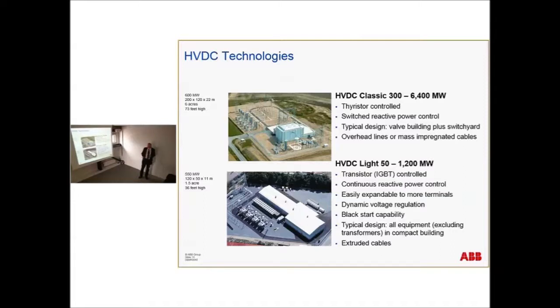The new technology, the VSC technology, the HVDC Light, is a transistor or IGBT controlled voltage source converter. Today it is available up to 1200-1500 megawatt. Here we can also control the reactive power, so it acts as a synchronous generator in the system. And it doesn't need any short circuit level on the receiving end. We can use the black start capability, and most of the equipment is located indoors, since there is no need of filters or capacitor banks. So the size will be considerably less compared to a similar HVDC Classic type.